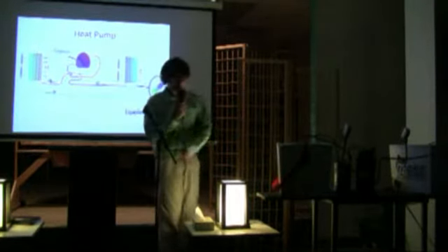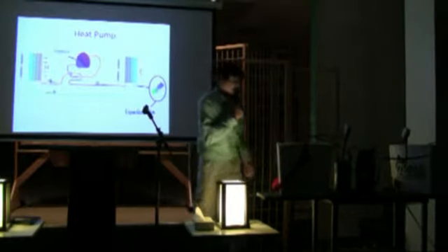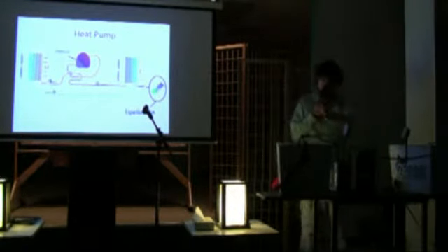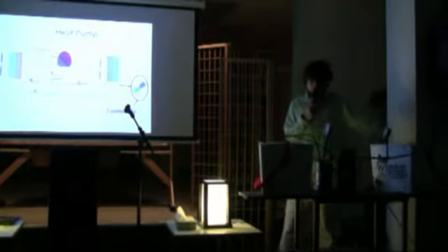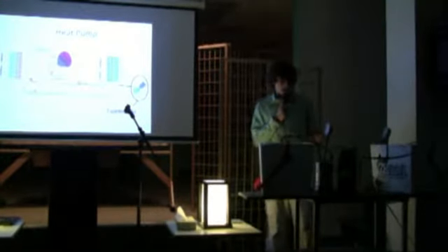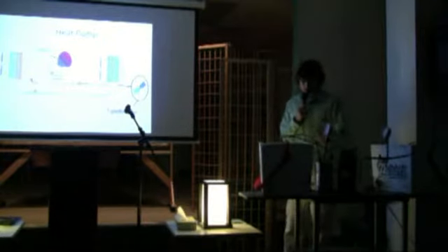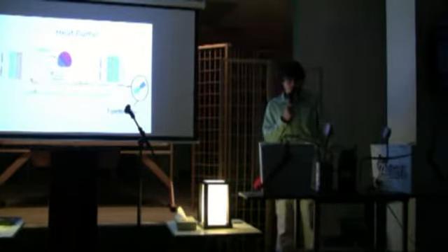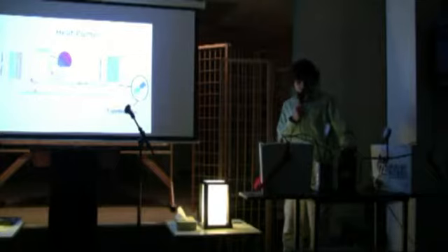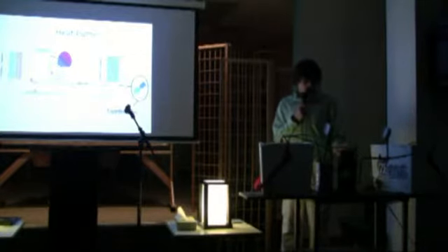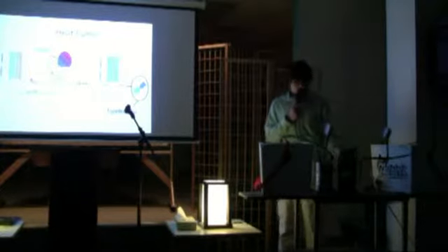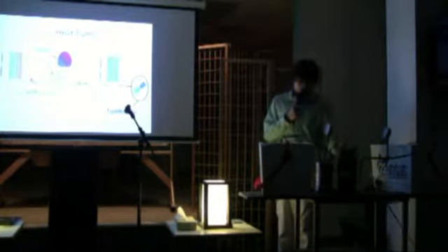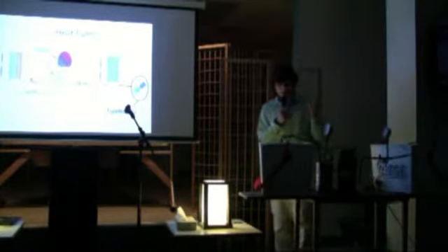Now what a heat pump does is it takes the heat from one side and moves it to another. So this is the cold side and this is the hot side, and how it does that is there's a refrigerant gas called Freon in the pipes, and first it starts out at the compressor, which does exactly what it sounds like. It compresses the gas, and when it does that, the gas is now under pressure. When gas is under pressure, it gets hot.